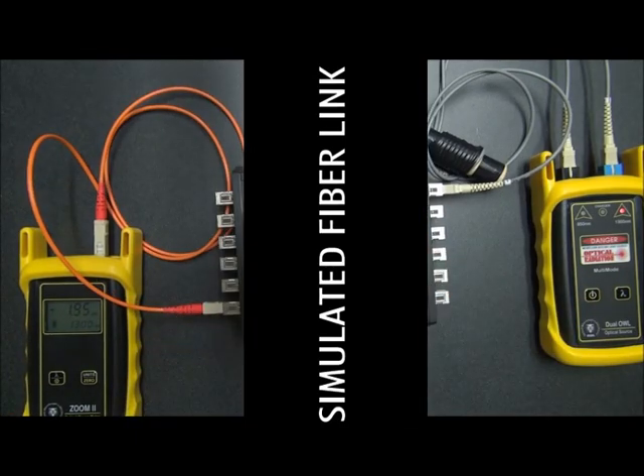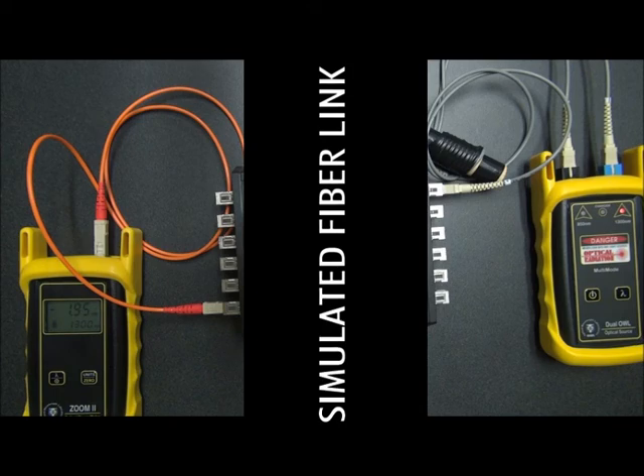Finally, we take the readings for the remaining fibers at 1300 nanometers. Some of these readings were fairly close to the pass-fail point, but they all passed. Once we're done recording all values, we can be assured that our link has been properly tested for insertion loss.